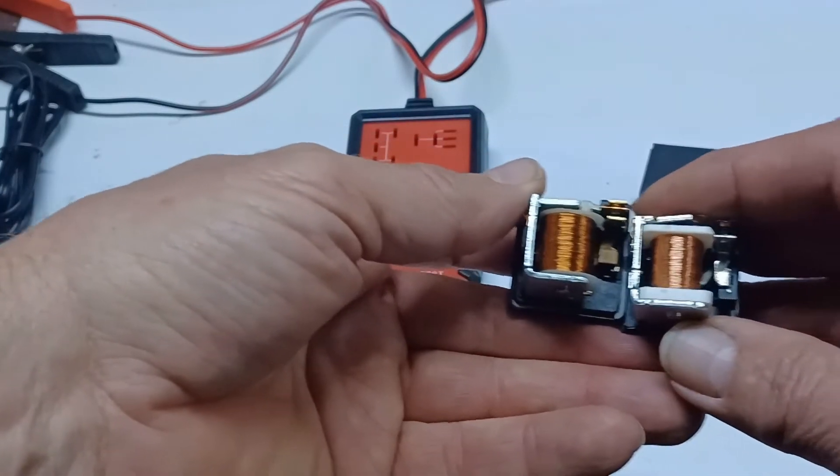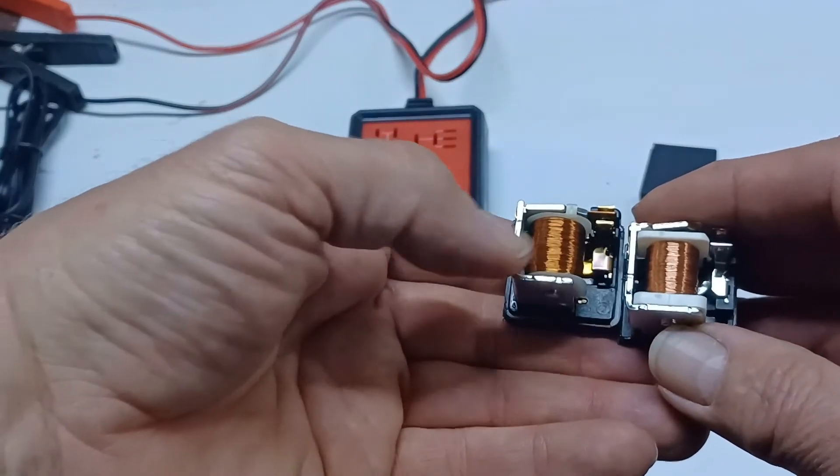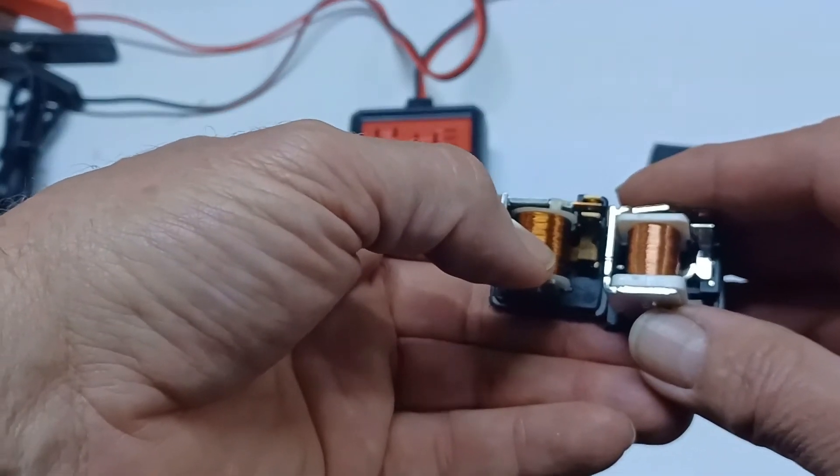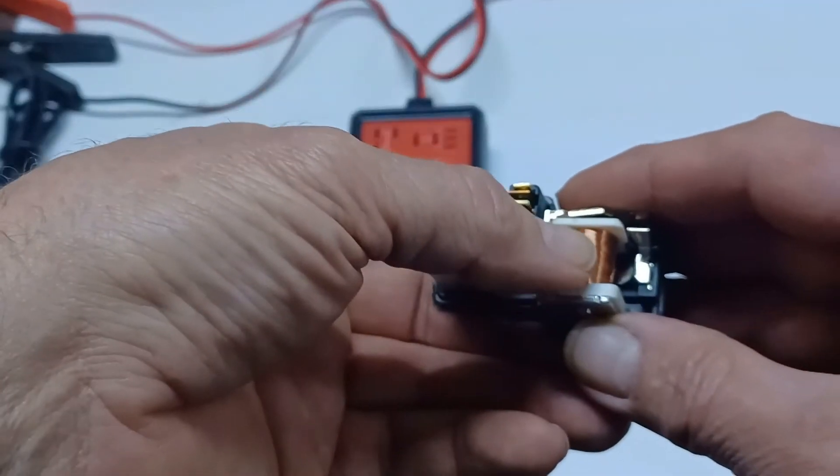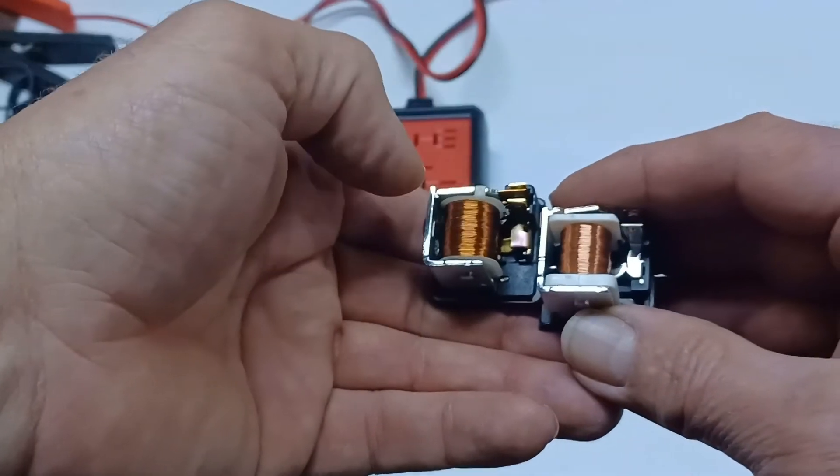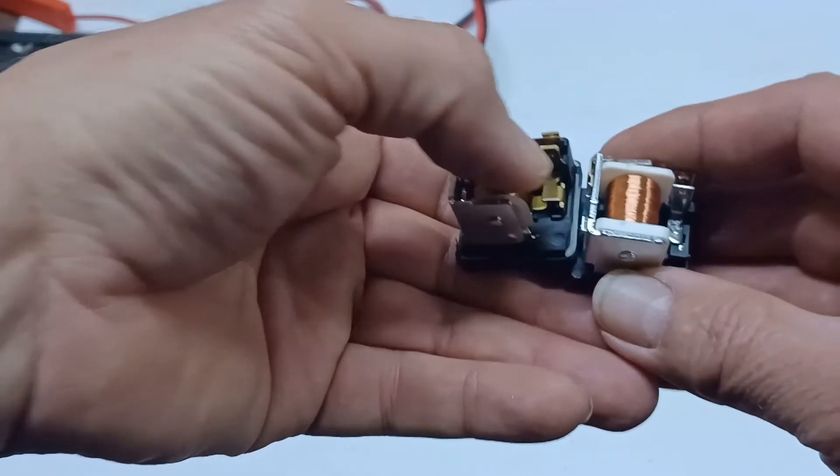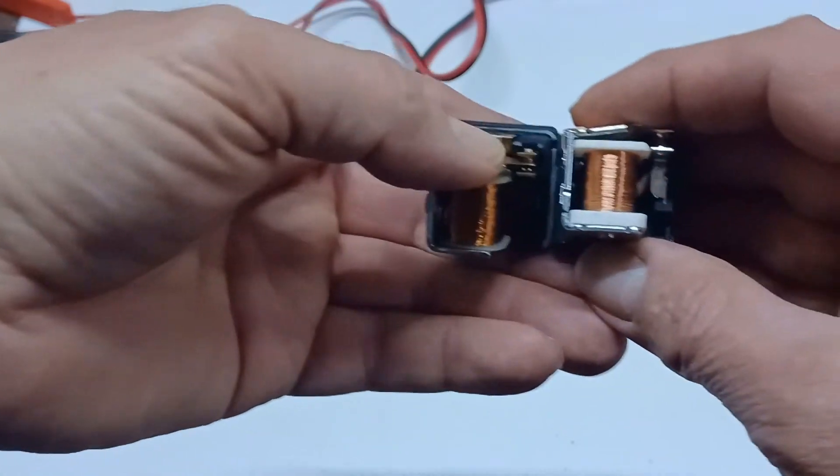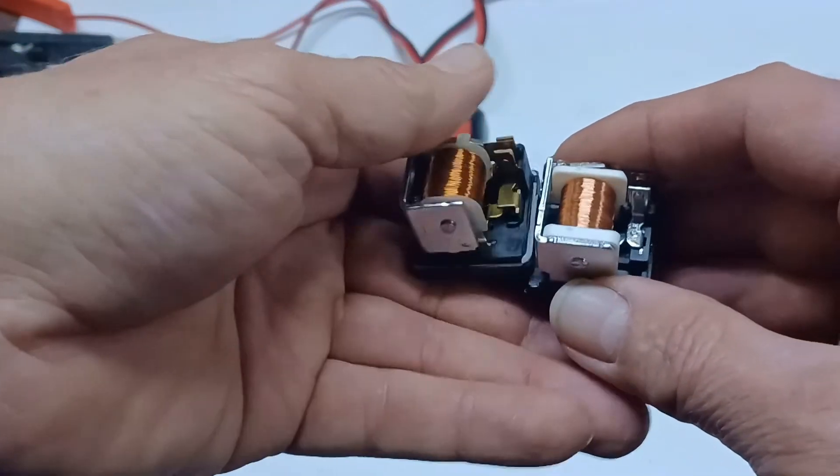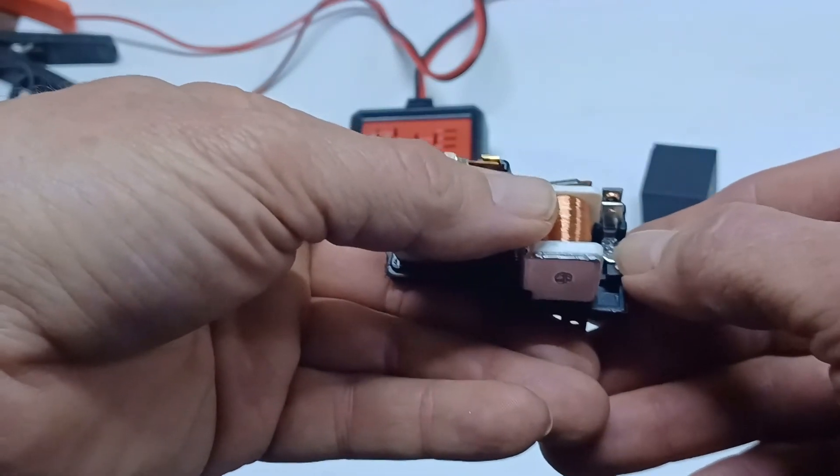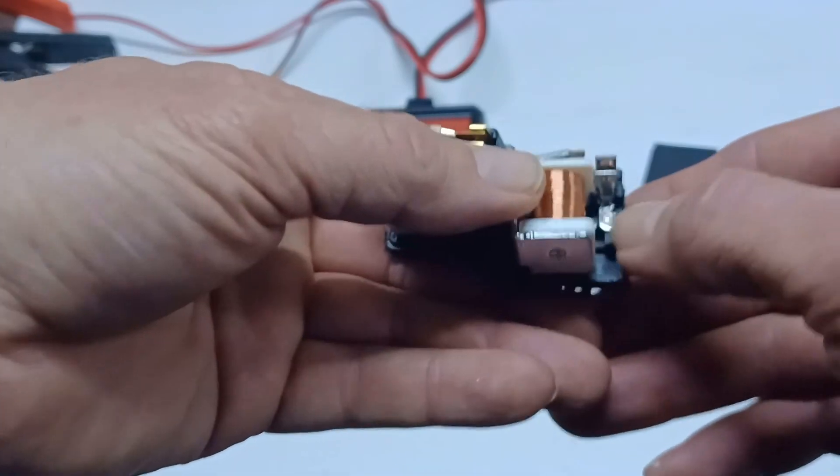So in comparing these two, I guess, we'll put them side by side. Now the one thing I see right off is there's a lot more windings on this magnet than there is on this one. So this one's going to be much stronger, of course, than this is to pull that down. The other thing I see too, is that all of our terminals seem to be brass in the Bosch unit and in the Chinese job, must be made out of recycled Hyundais because it just looks like a really cheap metal for their terminals.